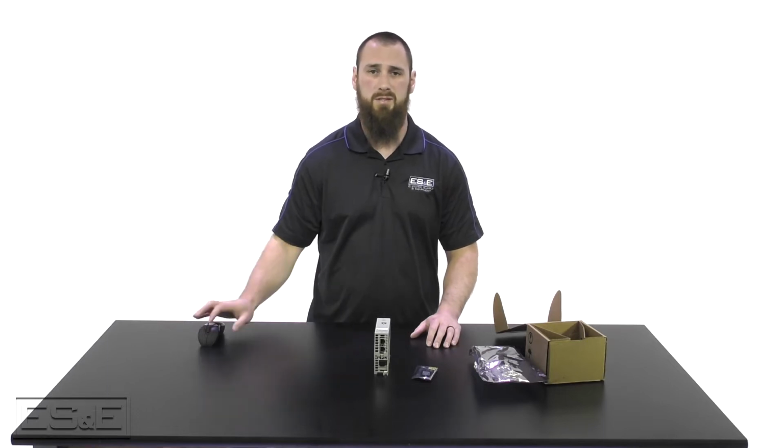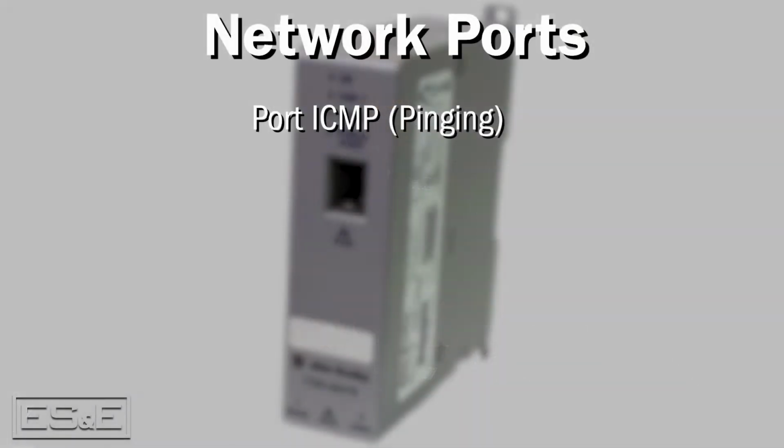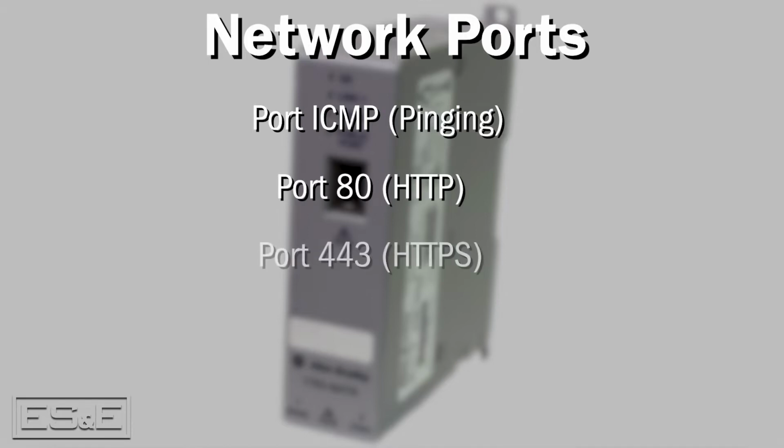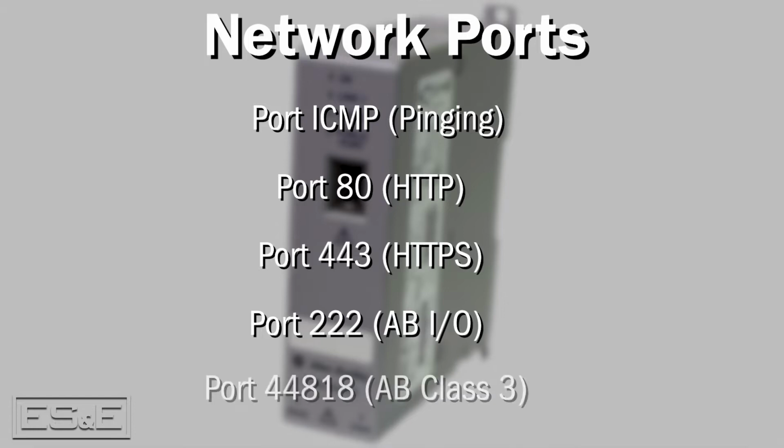of communications. There are 5 default ports, which are the ICMP for pinging, port 80, which is HTTP, which is the web, port 443, which is HTTPS, which is secure web, port 222, which is used for IO traffic for Allen Bradley equipment, and port 44818, which is for class 3 communications on Allen Bradley equipment.